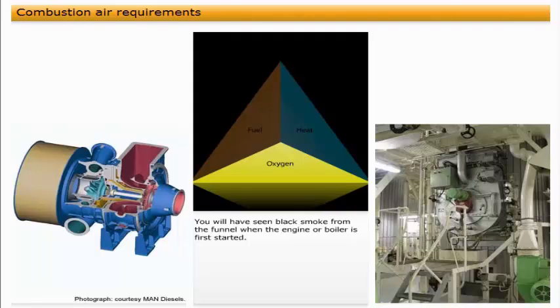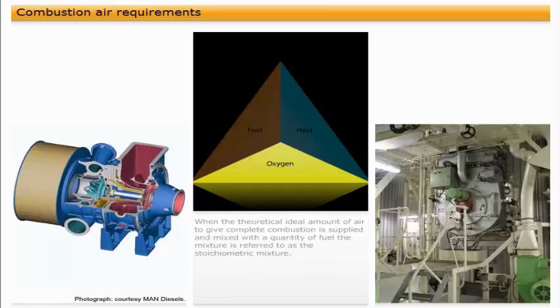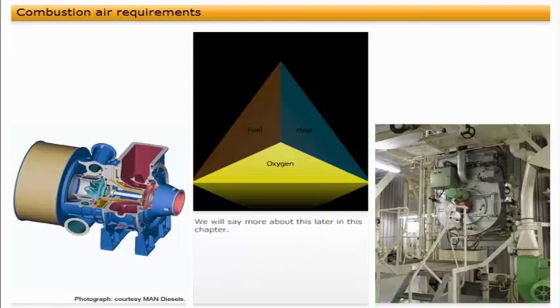You will have seen black smoke from the funnel when the engine or boiler is first started. This is usually due to the fact that insufficient air is being supplied at this stage for complete combustion. When the theoretical ideal amount of air to give complete combustion is supplied and mixed with a quantity of fuel, the mixture is referred to as the stoichiometric mixture. We will say more about this later in this chapter.